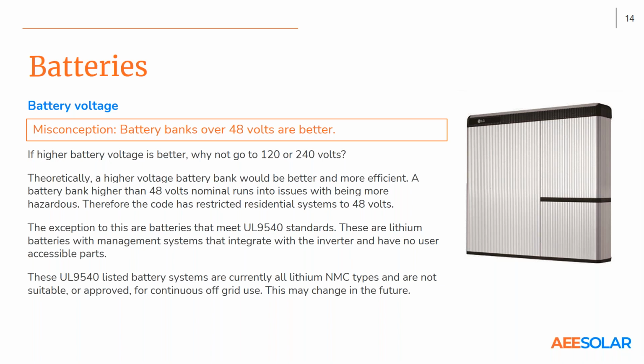Now, there are currently batteries, and actually they're called energy storage systems, ESSs, that meet the UL 9540 standard, and these are the grid tie systems that you see, the SolarEdge, LG, the Generac type systems, and they are also using a different type of lithium battery, and they're all very well integrated. They have solid communications between the inverter and the battery to make sure that nothing goes out of spec, and they don't have any user accessible parts. It's all engineered as a system.